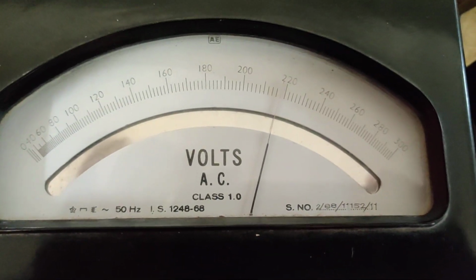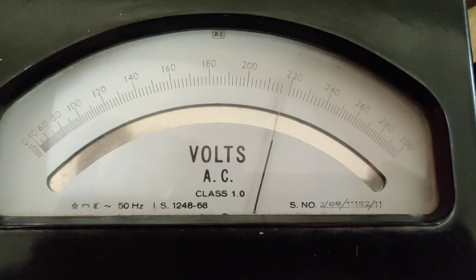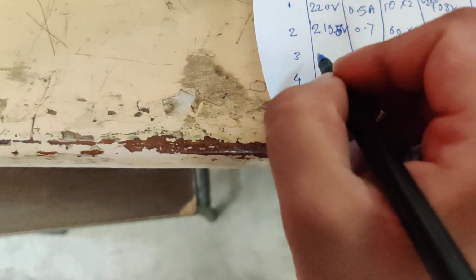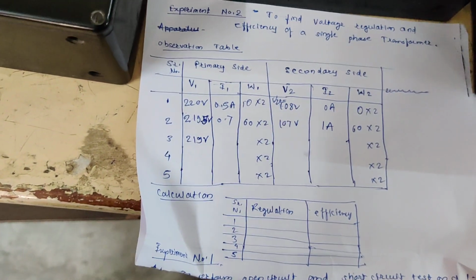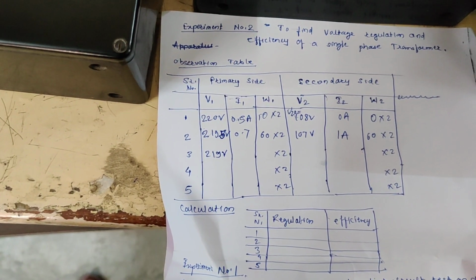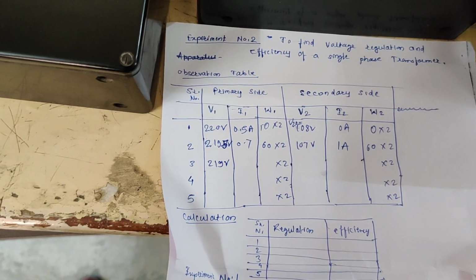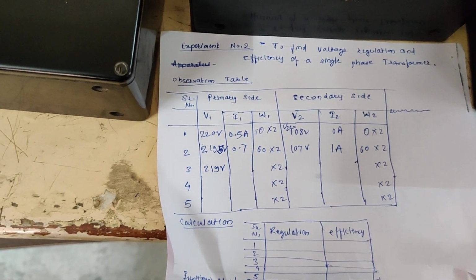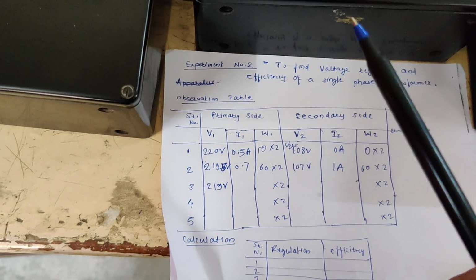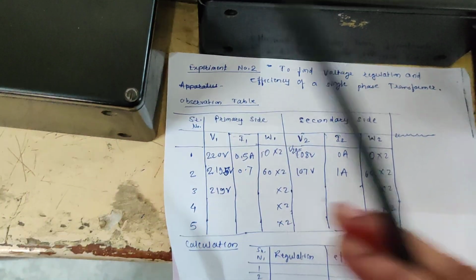So we have to start with the voltage across primary. It is 219 volts. Ideally we have to take number of readings. We have to take reading till one of the condition will match: rated current of primary or rated current of secondary.